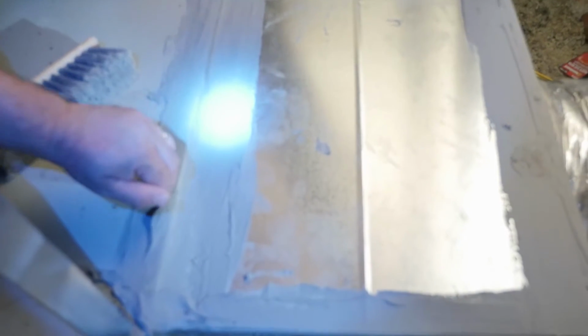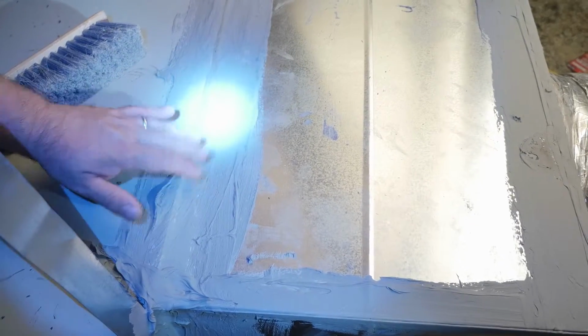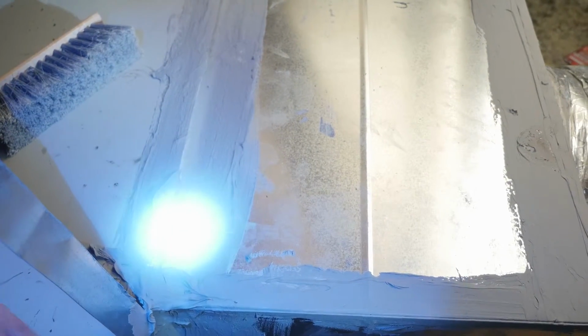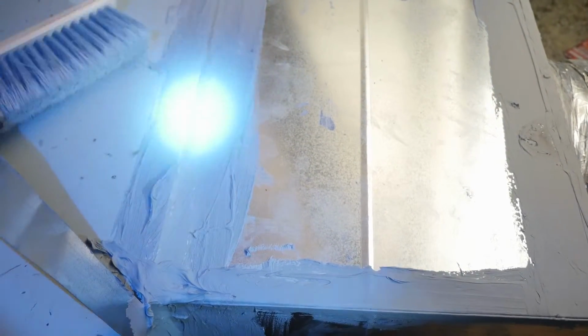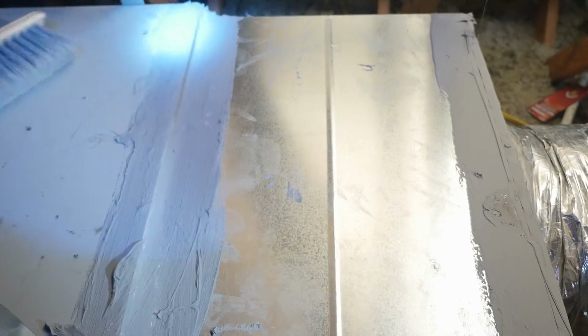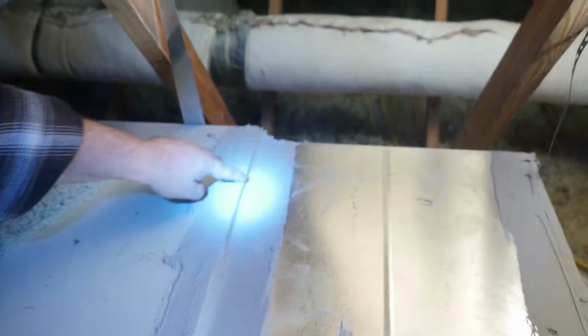You can see here that every seam on a furnace is painted with this sealant. This stops air from getting in where it's not supposed to, or any air from getting out. The only time they don't use this is where there's going to be an access panel. So as we're cleaning the debris from the surface of our furnace, we're going to make sure all of these seams are intact and not compromised.